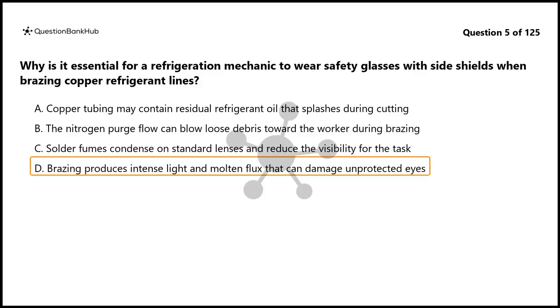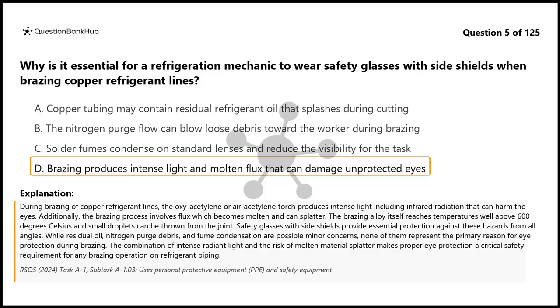The correct answer is D. During brazing of copper refrigerant lines, the oxyacetylene or air-acetylene torch produces intense light, including infrared radiation, that can harm the eyes. Additionally, the brazing process involves flux, which becomes molten and can splatter. The brazing alloy itself reaches temperatures well above 600 degrees Celsius and small droplets can be thrown from the joint. Safety glasses with side shields provide essential protection against these hazards from all angles.